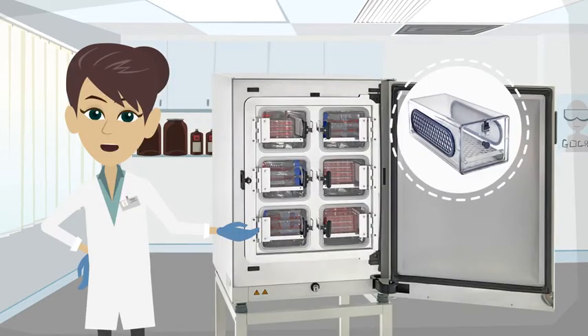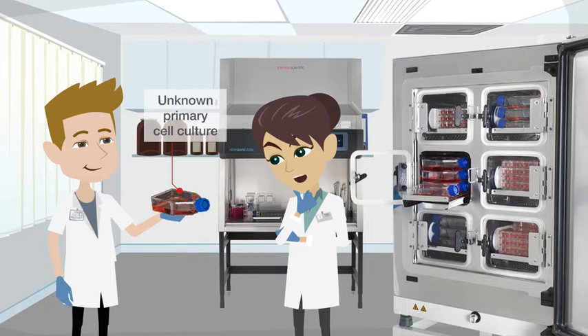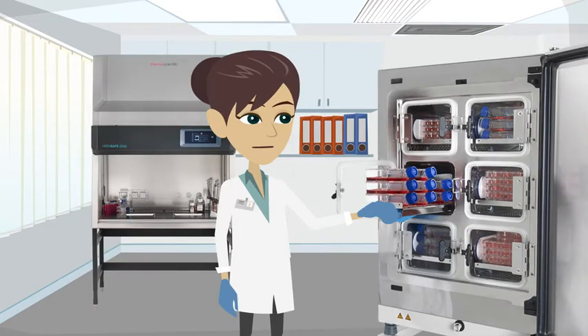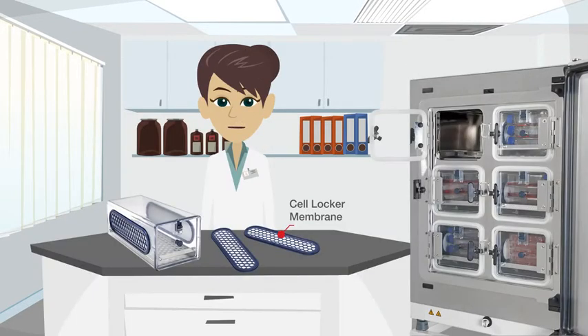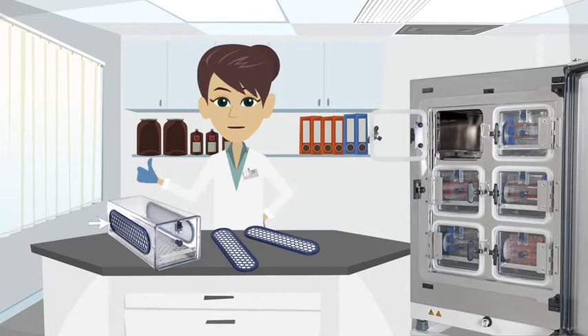With the Cell Locker System, the dual 0.2 micron membrane filters permit air circulation but exclude microbial contaminants. Cross-contamination of neighboring cultures or circulating microorganisms are a risk to your cell cultures. Cultures are segregated and protected within each individual chamber, effectively quarantining them from each other. Independent tests verify common cell culture contaminants including mycoplasma are unable to enter or exit the Cell Locker membrane.